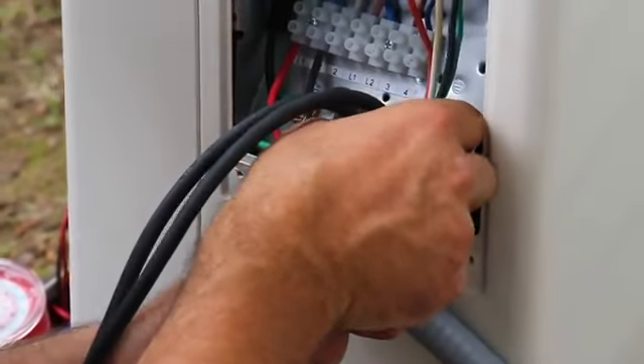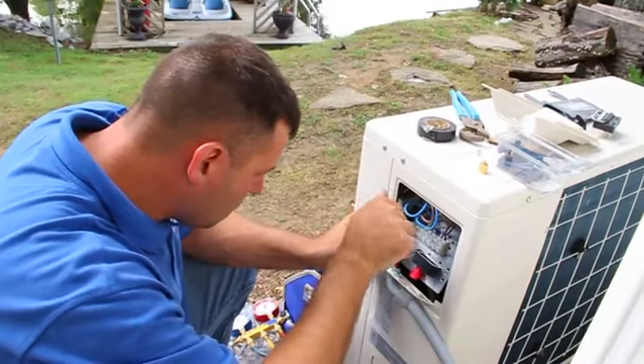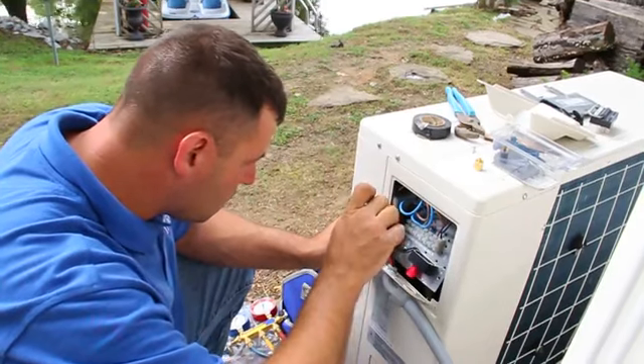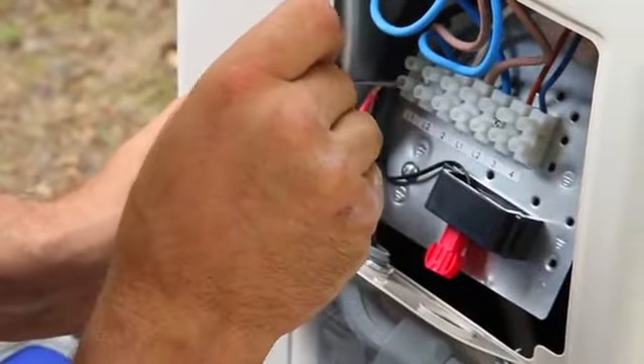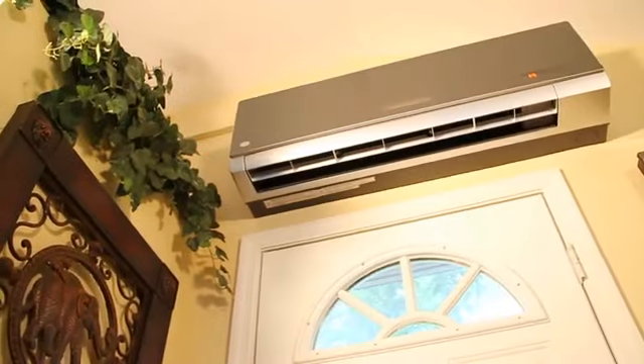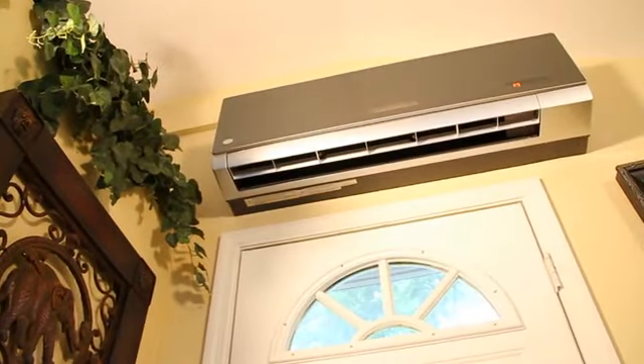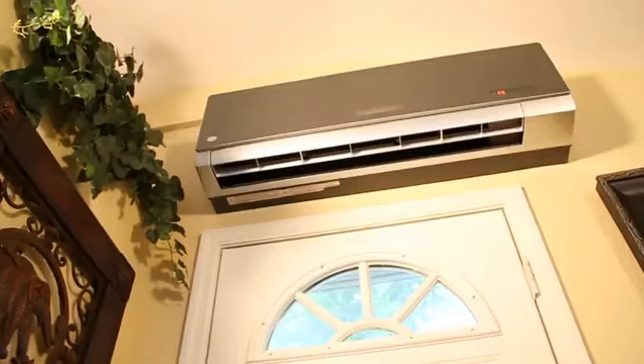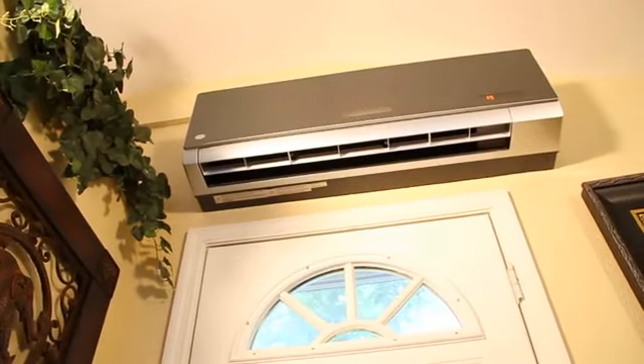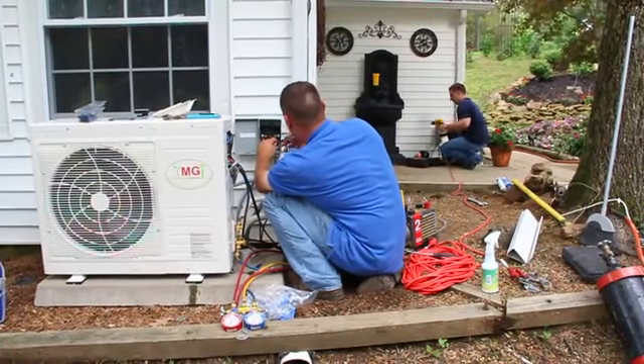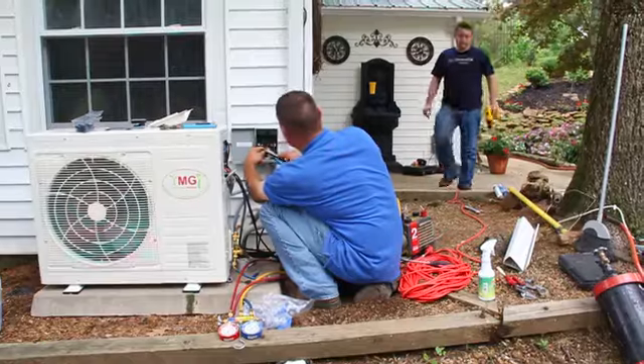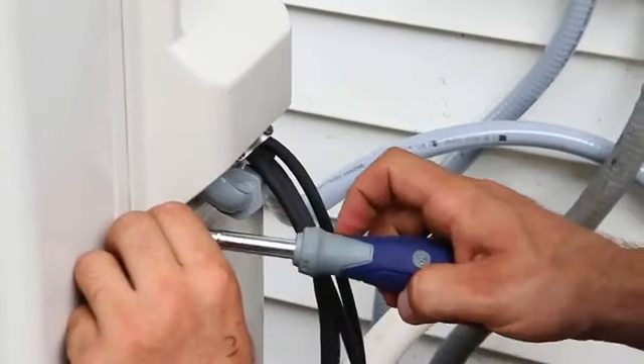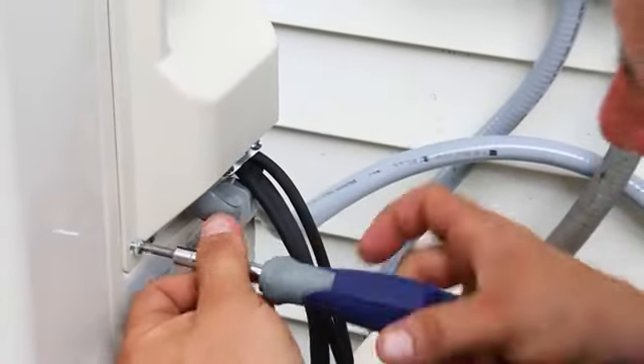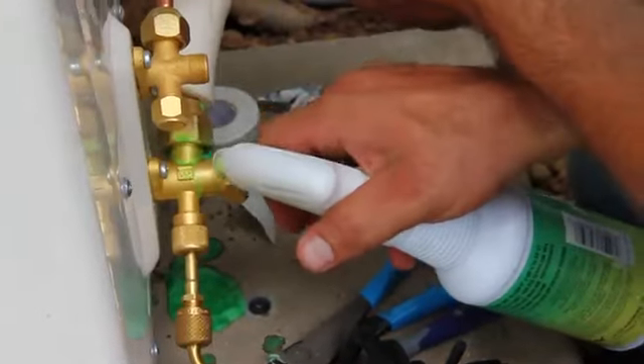Connect the low voltage wires first, making sure to do so according to any applicable electrical codes and safety considerations. With the outdoor unit connected, it is time to go back inside and connect the low voltage wiring to the interior unit. Again, do so in accordance with electrical codes. After making certain the outdoor unit is properly grounded, connect the high voltage wires and reattach the protective covering. The system should already be pressurized properly.